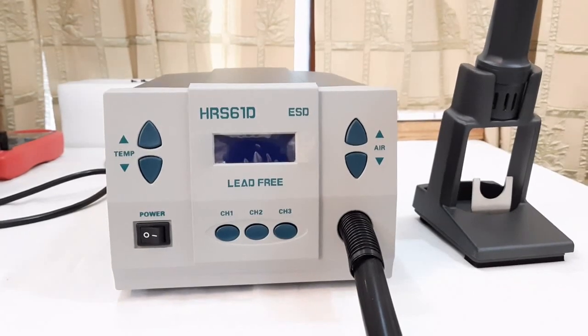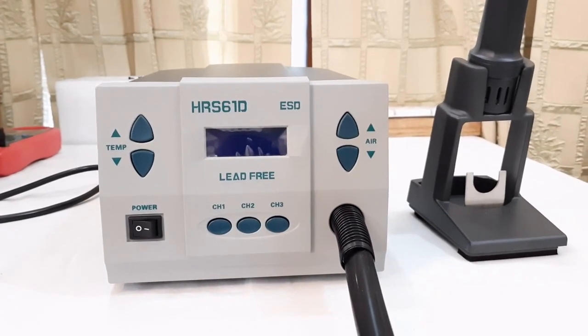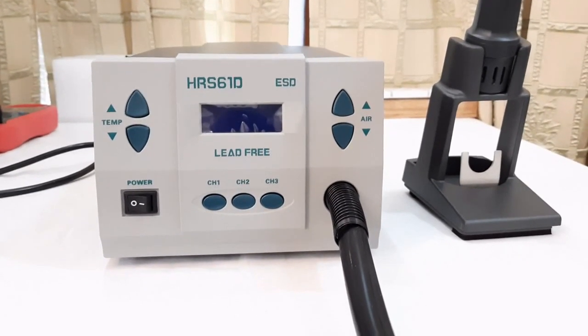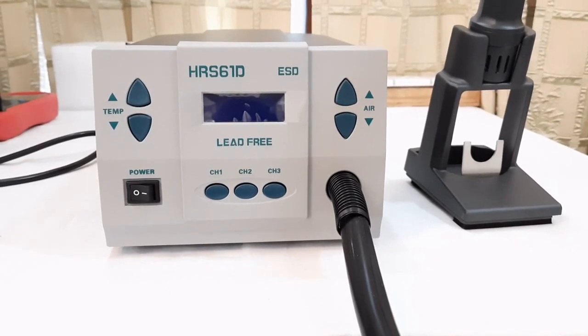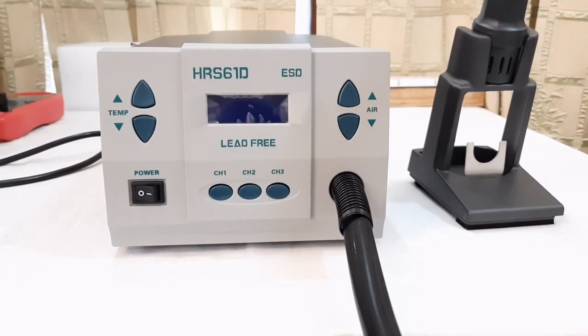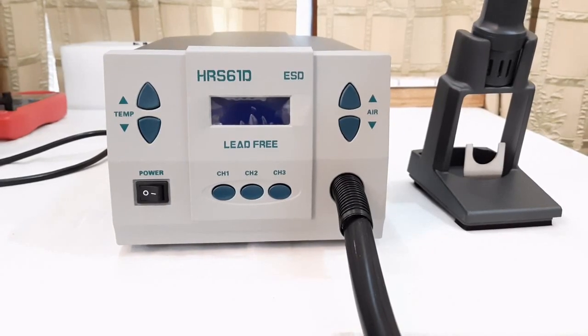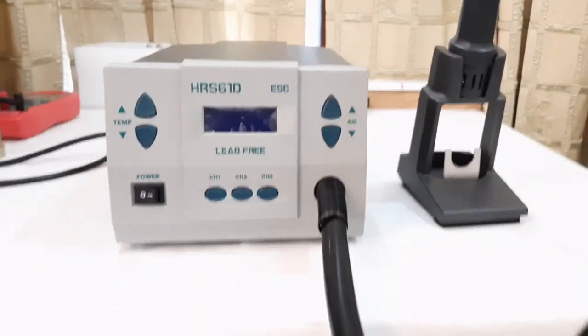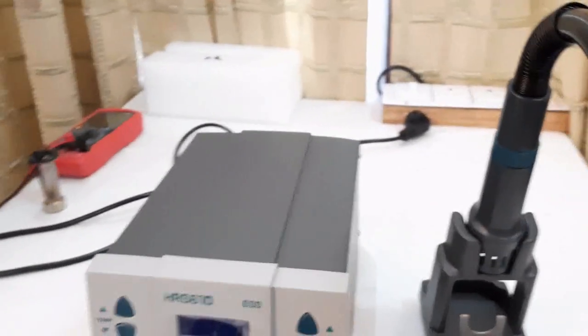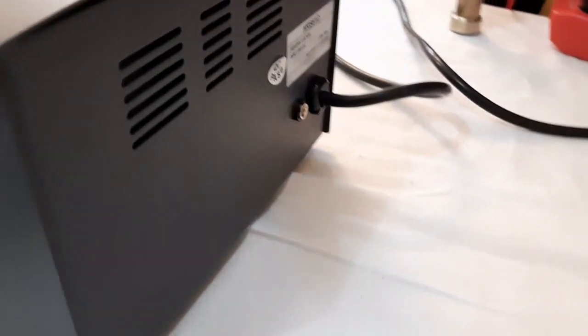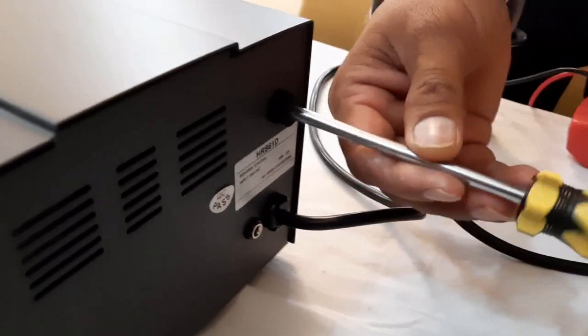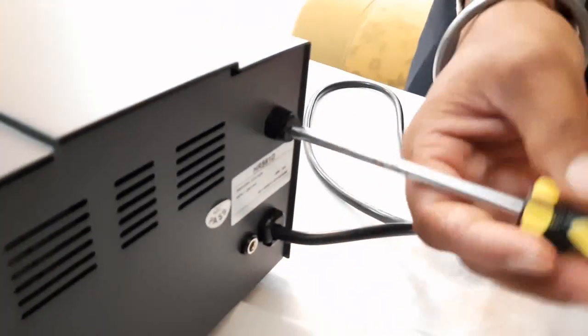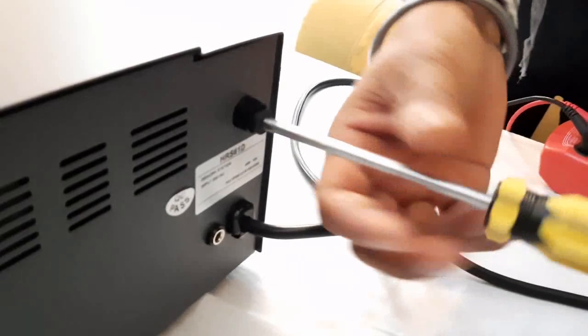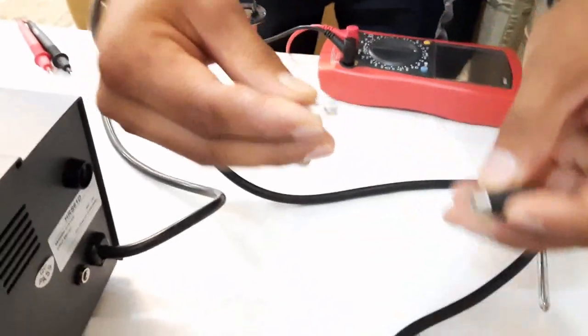Suppose the first error you might encounter is that this unit might not switch on. It might be some problem with the fuse. We need to check the fuse first. The fuse is located on the rear side of this unit. We need to take out the fuse with the help of this star screwdriver. We need to take out this fuse holder and check the continuity with the help of a multimeter.